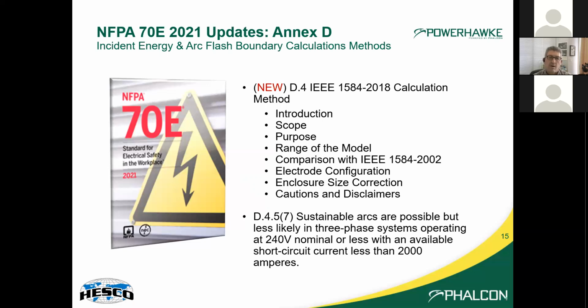The challenge is that these pieces, combined with section D.4.5(7) at the bottom, changed things. Under 1584-2002, we used a cutoff point where you'd go down into the system until you hit a point where the voltage was 240 volts or less, fed by a transformer of 125 kVA or less, which defined the lower limits of your analysis scope. The 1584-2018 has changed that, and now it's 240 volts or less and 2000 amps.